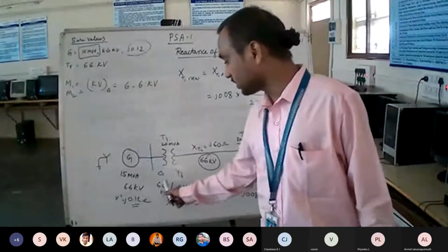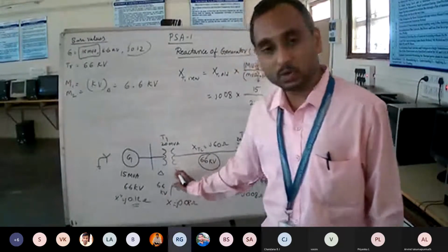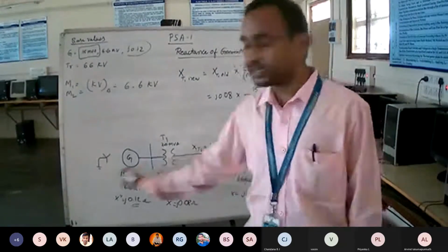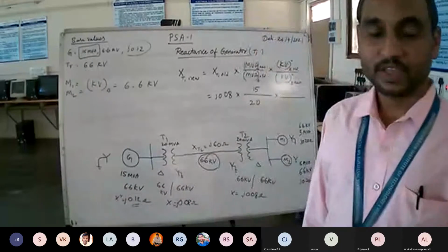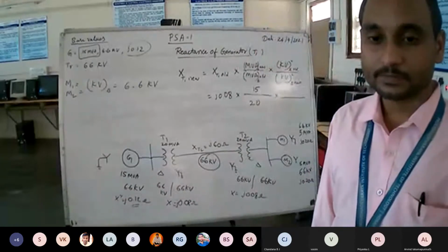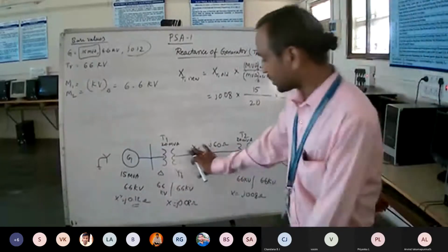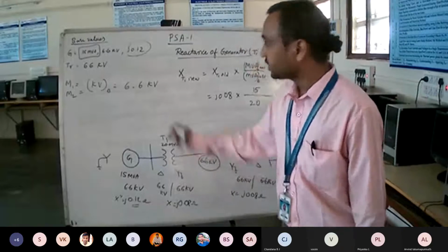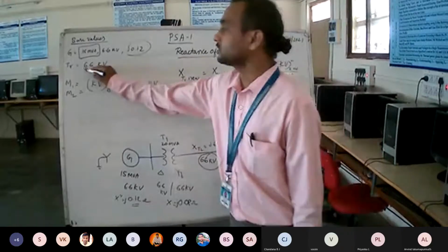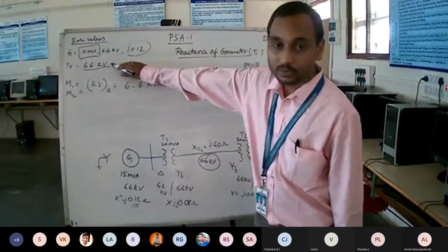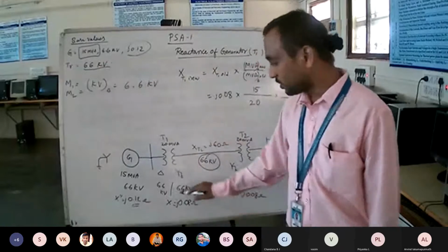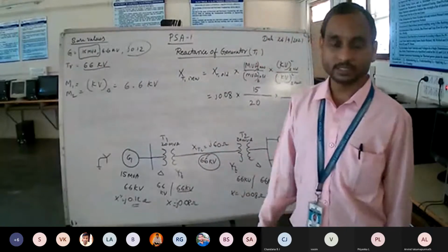It will be equal. So these are voltage ratios. Either you have to choose on the HT section or the LT section, any one section. Suppose you are calculating on the HT section, then the HT section base kV is 66. This is the new value you have calculated. Old value is also 66.